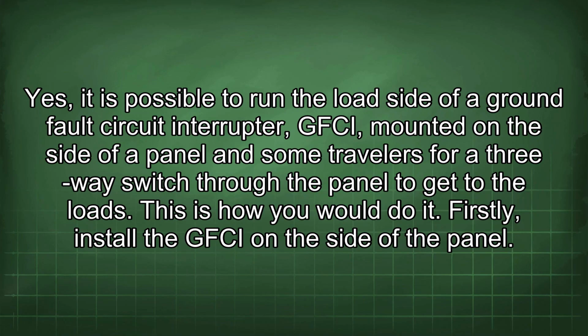Yes, it is possible to run the load side of a ground fault circuit interrupter (GFCI) mounted on the side of a panel and some travelers for a three-way switch through the panel to get to the loads. This is how you would do it.